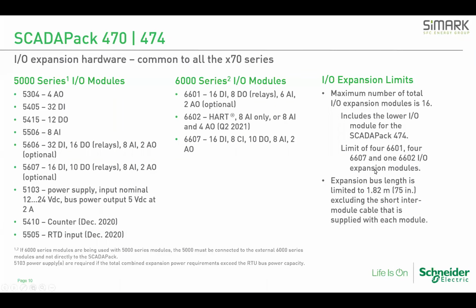So when adding expansion modules, you must be aware of whether you need a separate 5103 power supply to ensure all expansion modules on the bus get sufficient 5-volt power. There's a calculation to be done, so please work with myself or our other specialists at SIMARK when designing a system with expansion modules to make sure you don't need to add one of those.